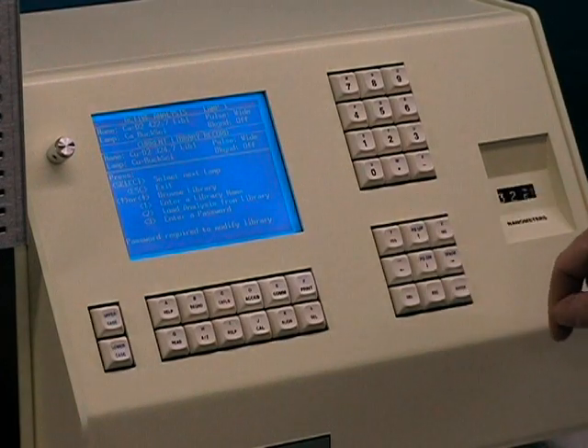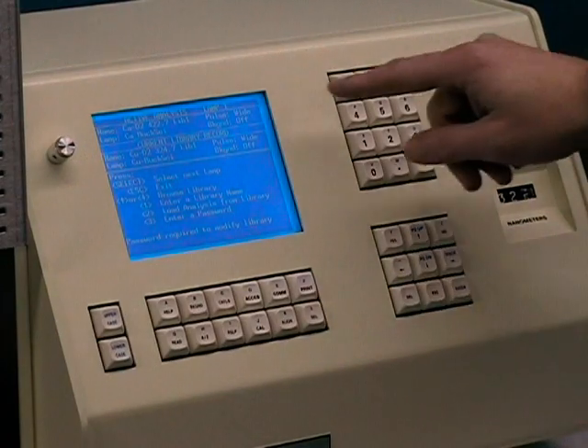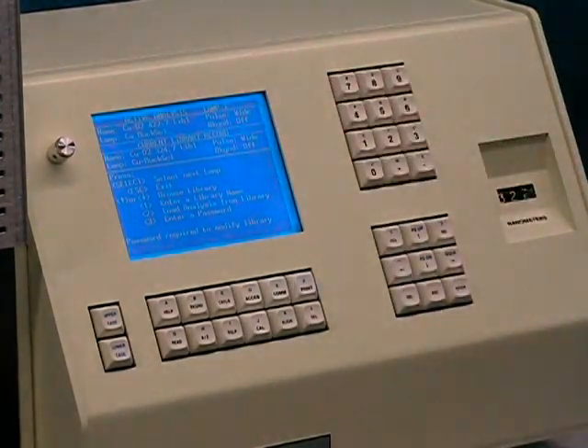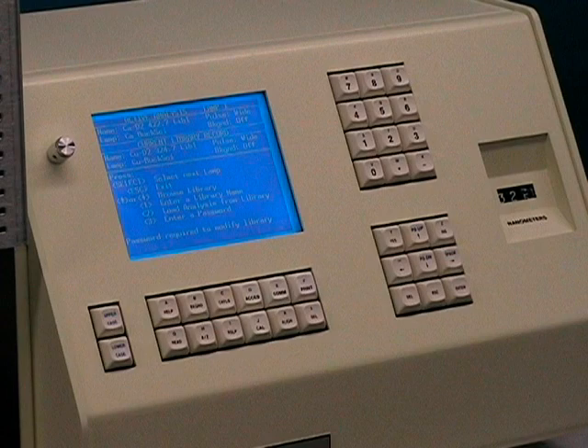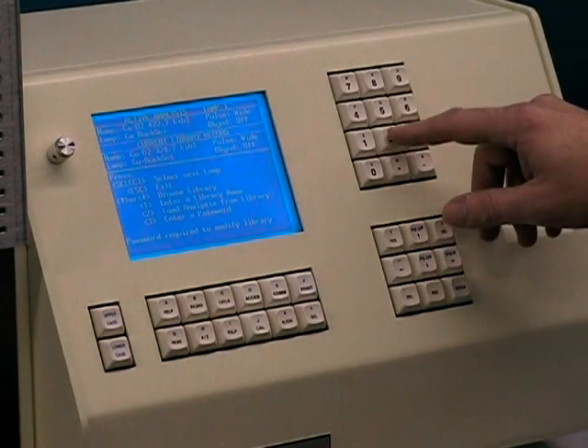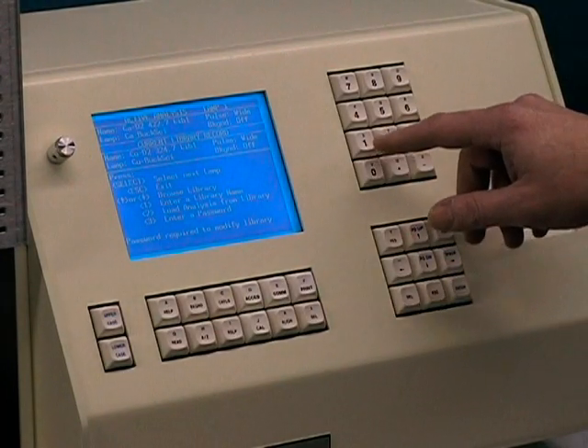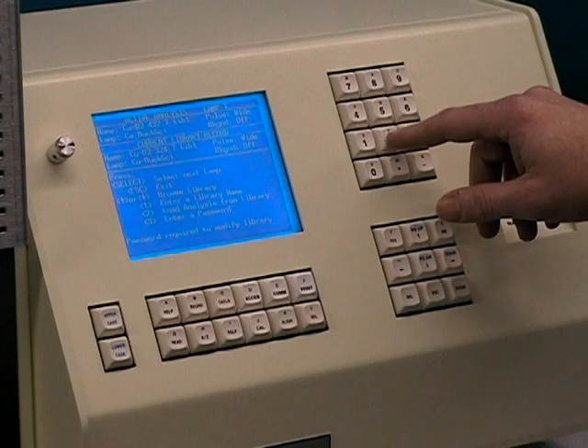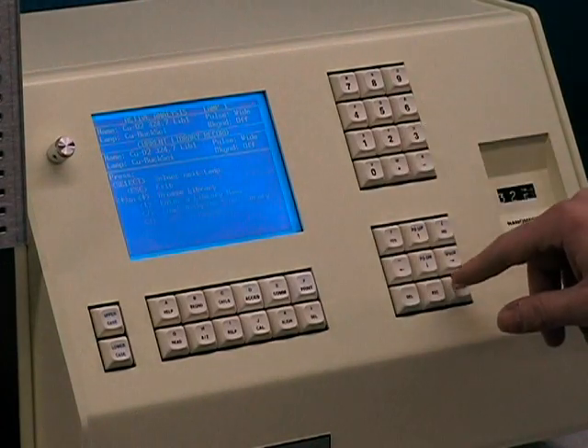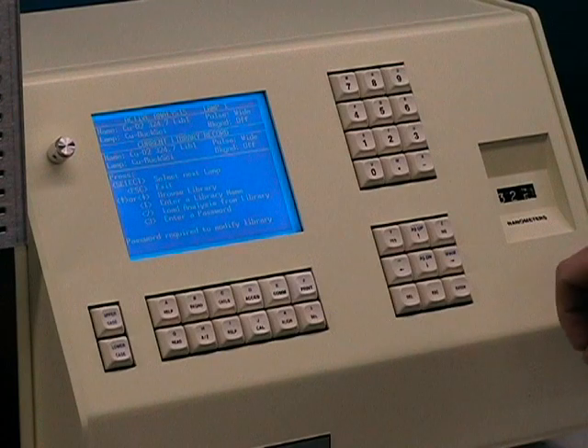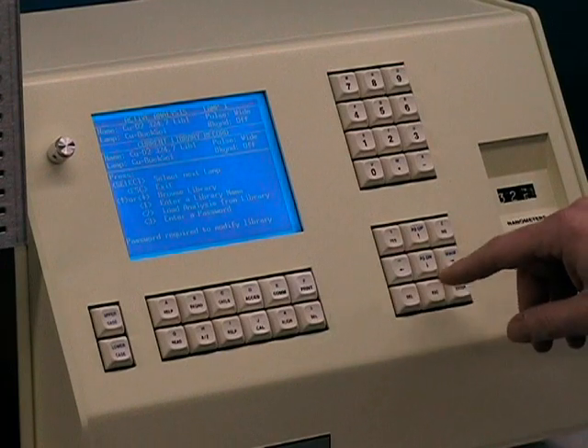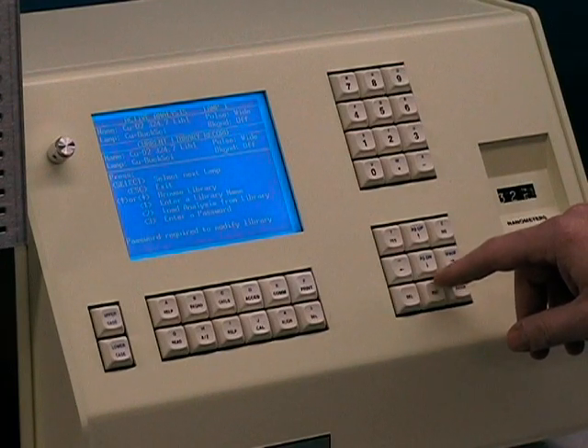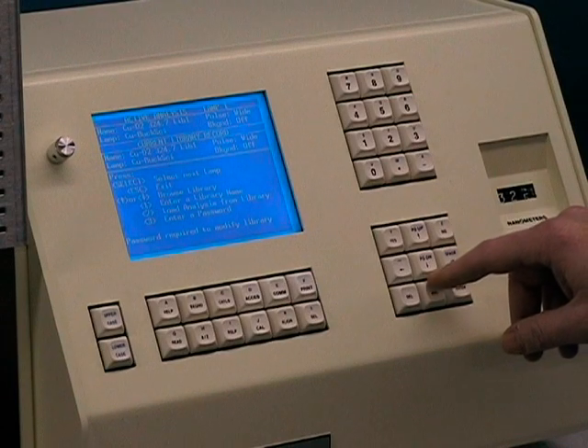Now notice in the upper right corner of the display, there's a lamp designation, lamp 1, lamp 2, and lamp 3. Make sure the proper lamp is loaded with the hollow cathode lamp based on the file you select in the library. In this case, we're selecting copper for flame work. By pressing 2 and enter, it replaces the previous file, which was calcium, with copper, and you can see that in the upper line of the display. Once this is done, press escape.